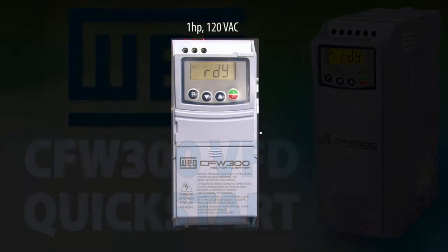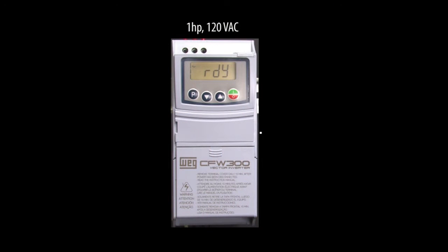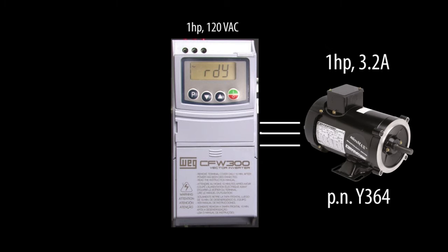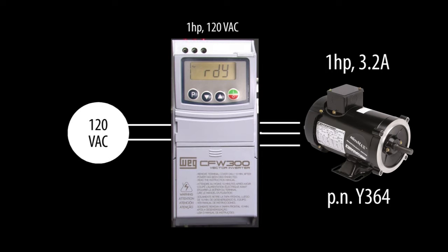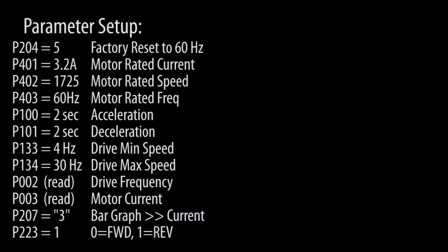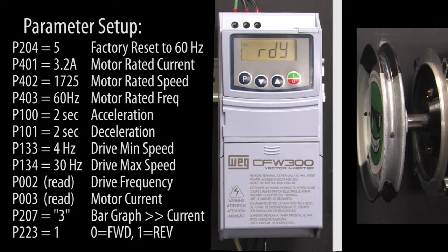In this video we'll use a 1 horsepower WEG CFW300 drive to control a motor from a single phase 120 volt supply. These are the parameters we're going to set and the values we're going to use in this demo. Let's quickly walk through setting these just so you can get a feel for the flow of entering parameters.